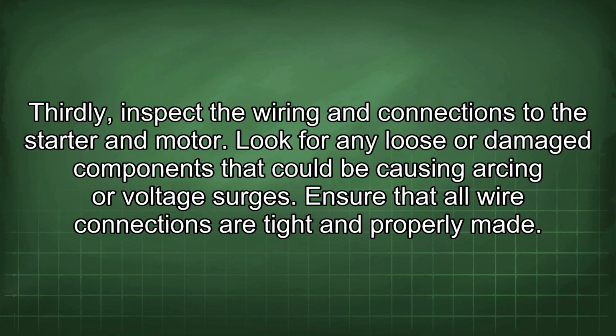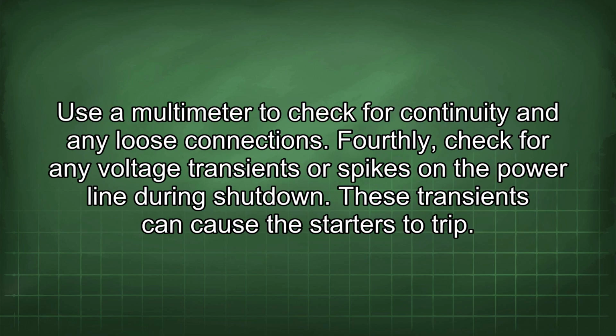Thirdly, inspect the wiring and connections to the starter and motor. Look for any loose or damaged components that could be causing arcing or voltage surges. Ensure that all wire connections are tight and properly made. Use a multimeter to check for continuity and any loose connections.